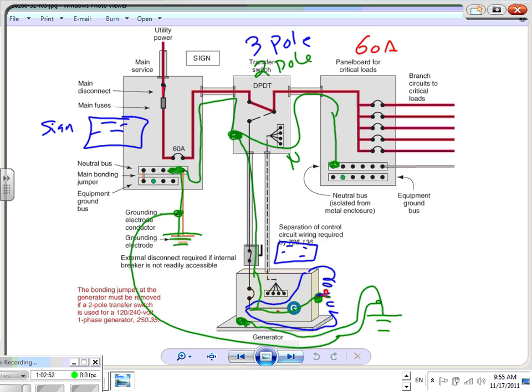So a firefighter walks in and wants to fight the fire, and they say, here's my disconnect. Look what happened when I disconnect this. If this is an auto transfer switch, it will start the generator. So when I walk in to fight the fire, I can see a sign: another source of power is here, and the location is in the backyard. So I go in the backyard and also disconnect the two sources of power. That's safety. That's sign number one.